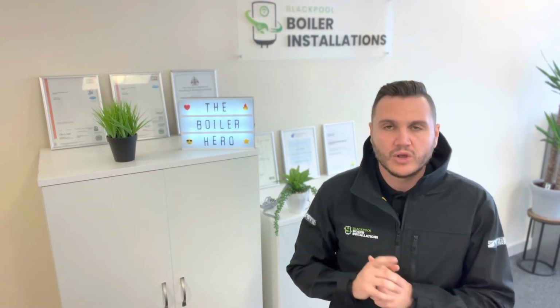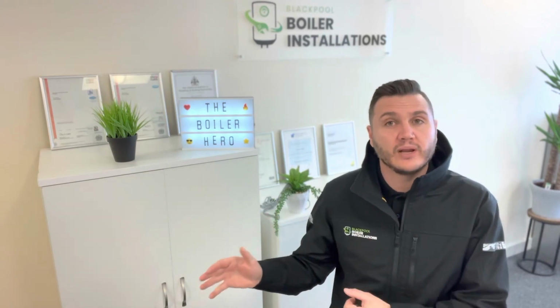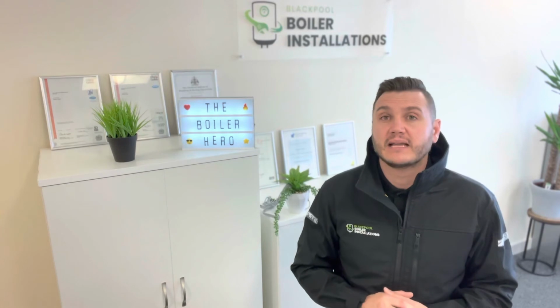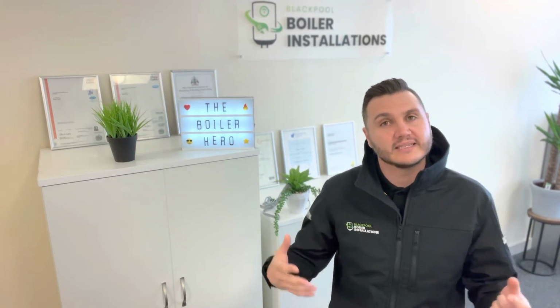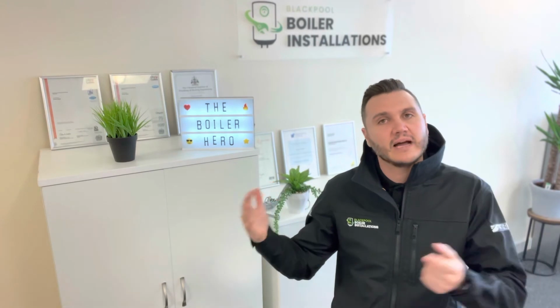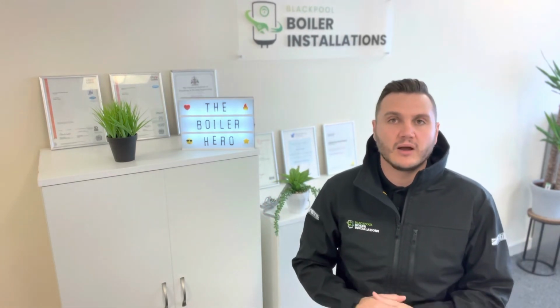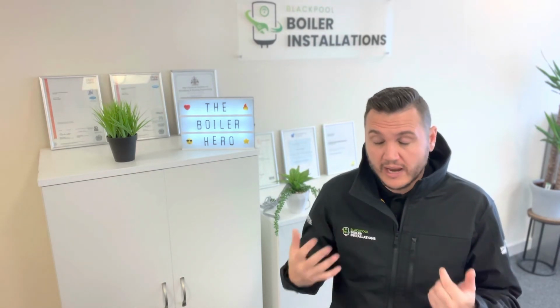You may have an old radiator valve or even an old shower that was fine before. You have a new combi boiler and all of a sudden the shower drips or a radiator leaks, and it's because the new pressure of the system is causing the old O-rings and seals to leak, because they've been used to running on low pressure gravity for 20, 30 years. Now all of a sudden you've converted the system to a combi boiler. It's rare, it happens now and again, but it's something to be aware of.